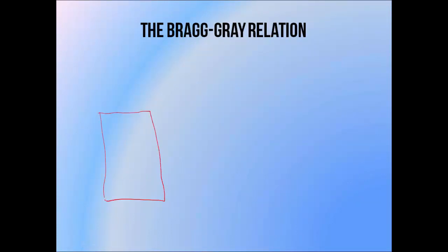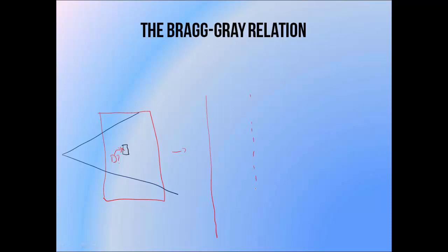We need the Bragg-Gray theory because if you want to measure dose at a point, all we can really do is put an ion chamber near it and measure the dose of the air volume. Dose is deposited mostly by secondary electrons at this point in homogeneous water without an ion chamber in place. The dose at this point, or depth, would be deposited by these secondary electrons here.